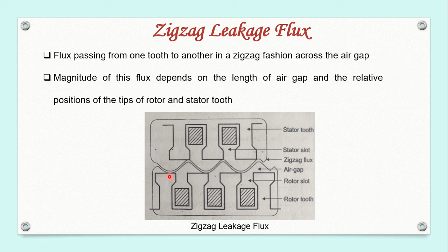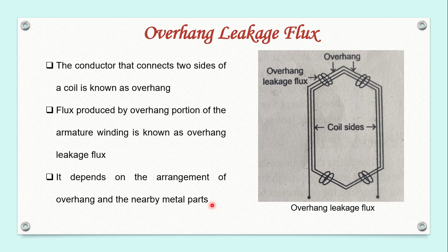Next one is overhang leakage flux. All of you know what overhang is. I have shown you the figure of overhang. Overhang is nothing but the conductor that is used to connect two coil sides. So this is a particular coil. This is one side of the coil, and this is the other side of the coil. The conductor that connects these two coil sides is known as the overhang. These two coil sides will be embedded in slots and the overhang will be present outside the slot. The flux produced by this overhang portion is known as the overhang leakage flux. The amount of this flux depends on the arrangement of the overhang as well as the presence of metallic parts near the overhang.